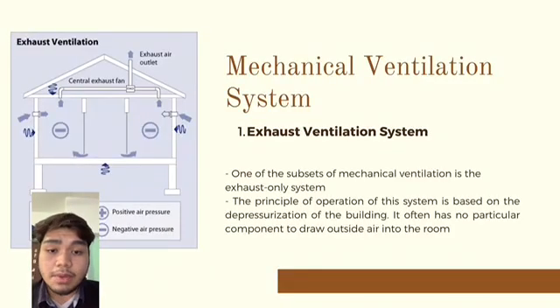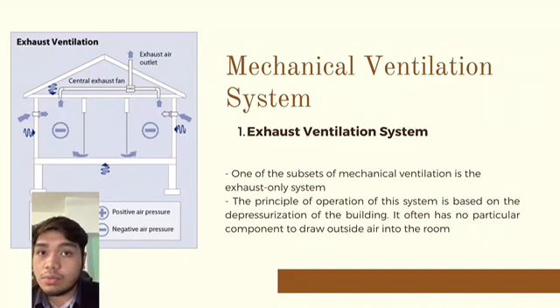Mechanical ventilation system. The first one is the exhaust ventilation system. One of the subsets of mechanical ventilation is the exhaust-only system. The principle of operation of the system is based on the depressurization of the building. It often has no particular component to draw outside air into the room. By decreasing the indoor air pressure below the outdoor air pressure, the outside air will enter the room through leaks in the walls and windows. The exhaust ventilation system is suitable for cold climates. If you use this system during hot, humid summers, the reduced pressure can draw moisture into the building and wall cavities, where it can cause condensation damage.